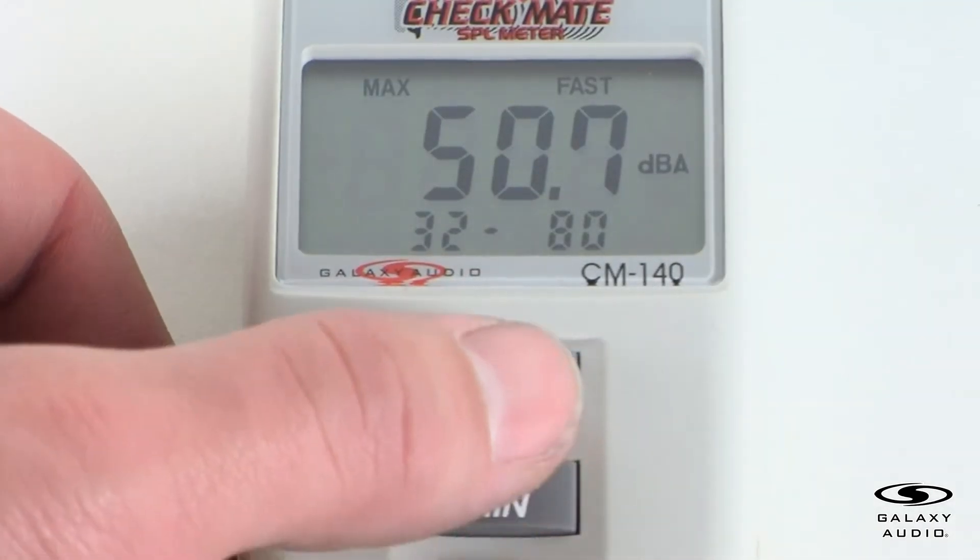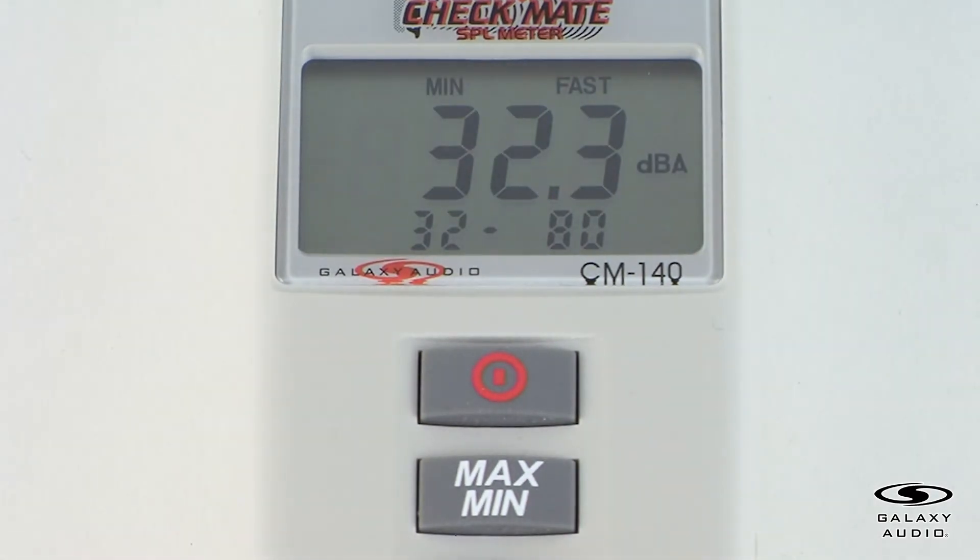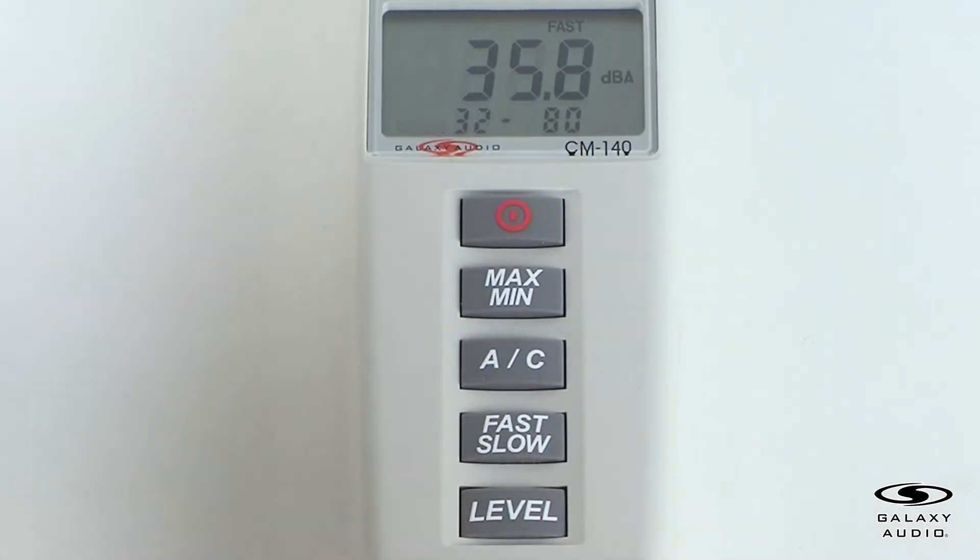For the max-min button, the CM140 can register the maximum and minimum levels encountered during use. First, select the proper level range before using the max-min to ensure that the reading value will not exceed the measurement range.